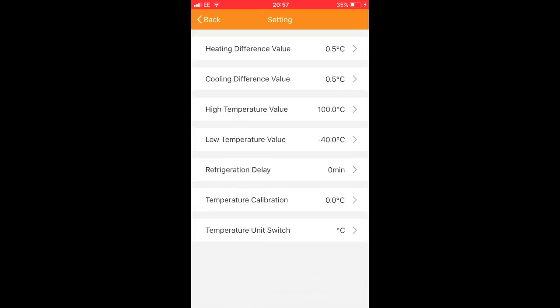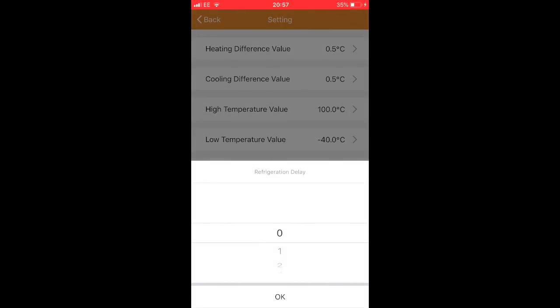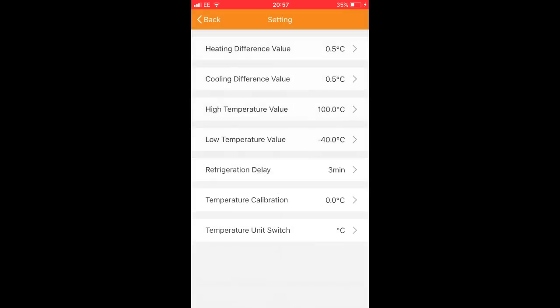Refrigeration delay is a delay time for the compressor, so most people recommend you set this to at least a few minutes, so that if your temperature is flip-flopping around, you're not going to burn out the compressor by switching the fridge on and off continuously. So I'll put that to 3 minutes.